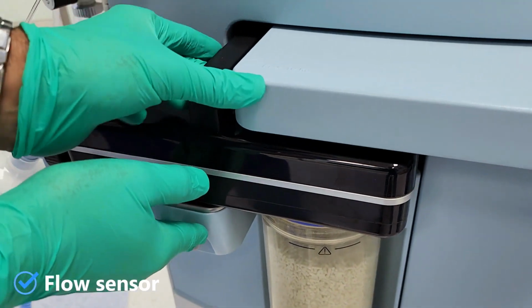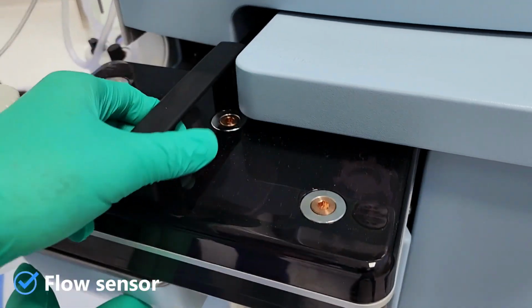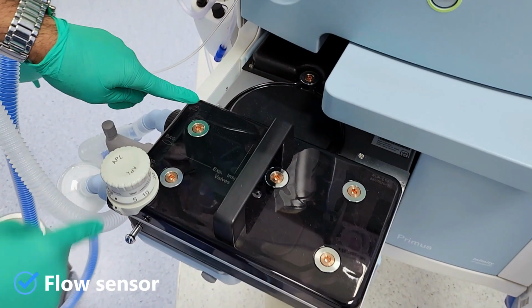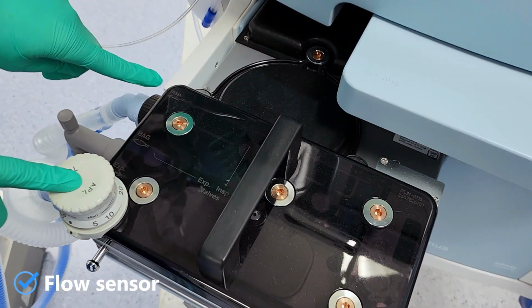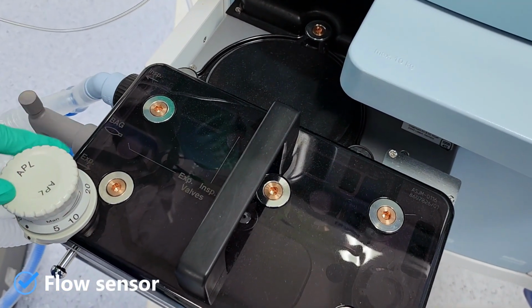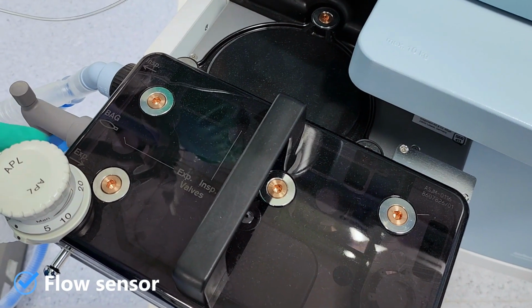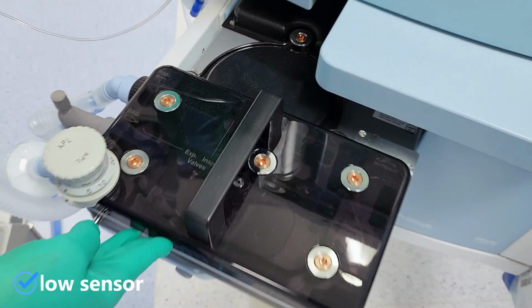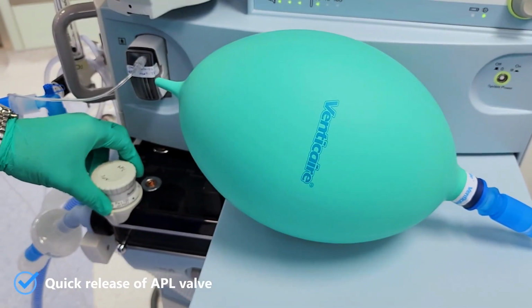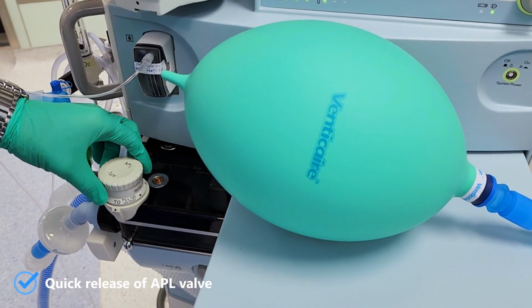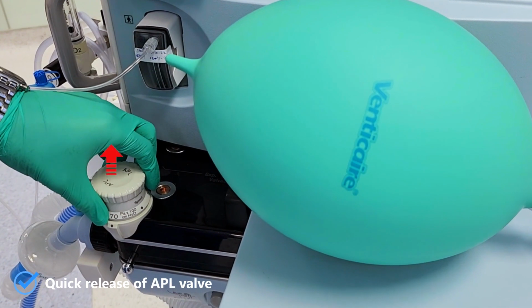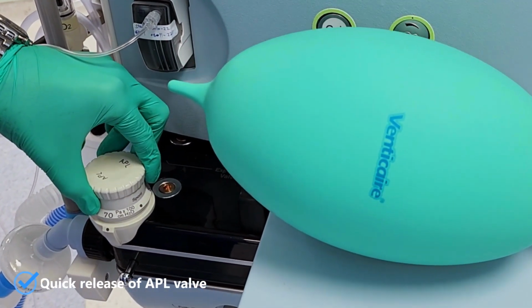There are 2 flow sensors inside the breathing system, one for inspiration and one for expiration. To change the flow sensor, we have to unlock the breathing system and pull it out, then open the cover using an Allen key to change the flow sensor. Coming to safety features. One of the safety features in this machine is quick release of the APL valve. Just pull up for quick pressure release.